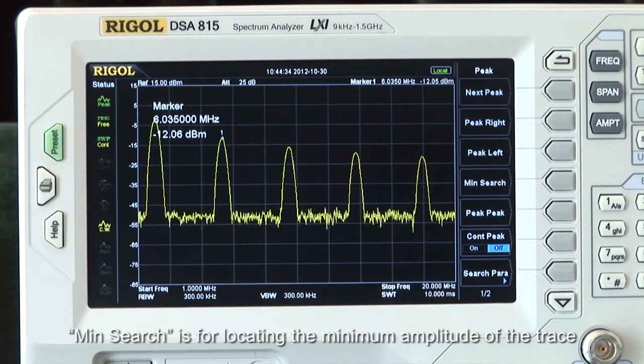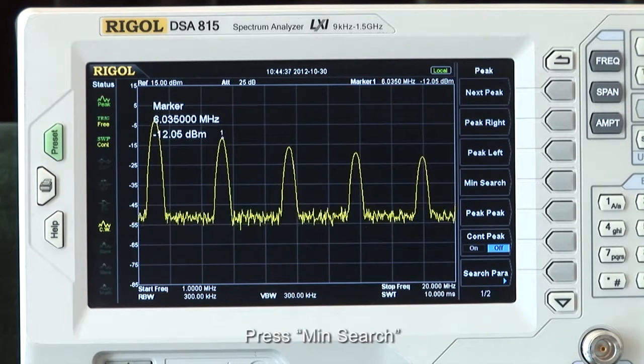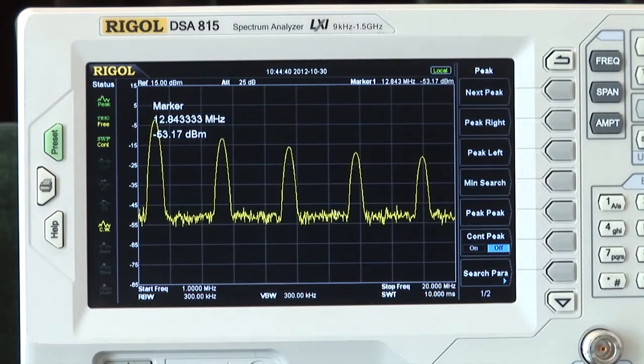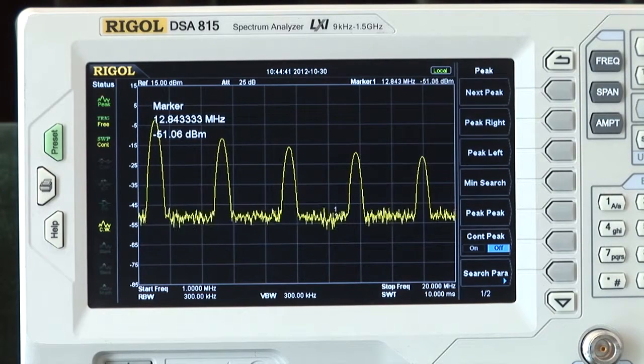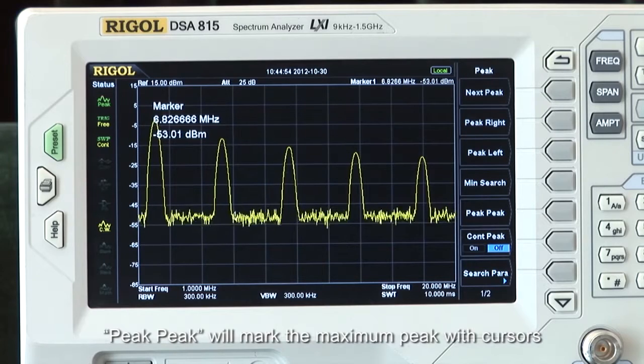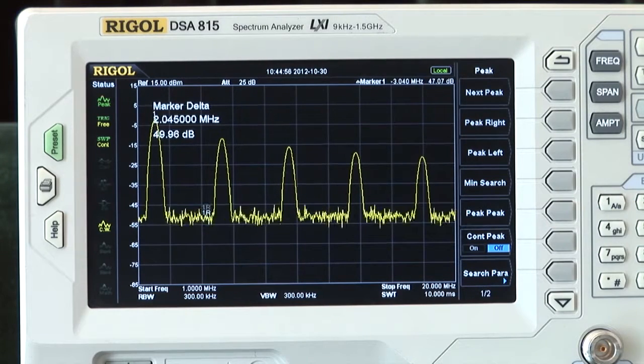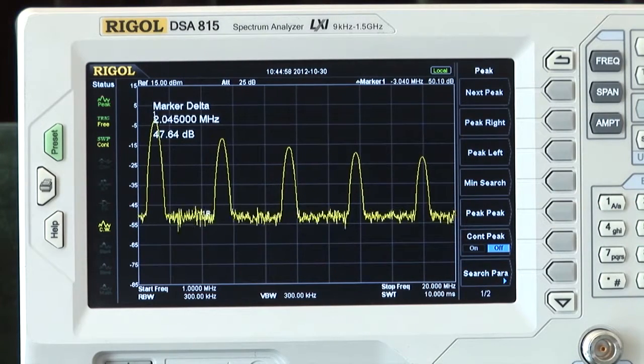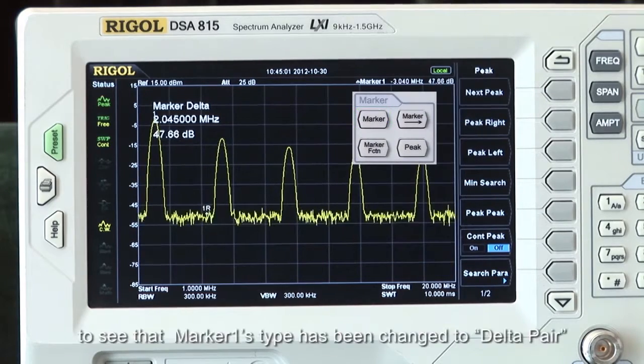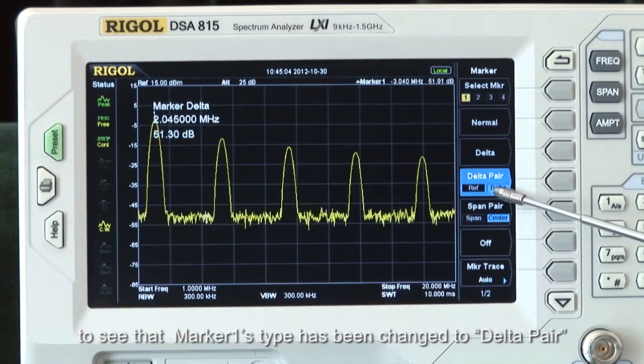MinSearch is for locating the minimum amplitude of the trace. Press MinSearch, and the marker appears at the minimum amplitude. Peak Peak will mark the maximum peak with cursors. Open the marker menu to see that marker 1's type has now been changed to delta pair.